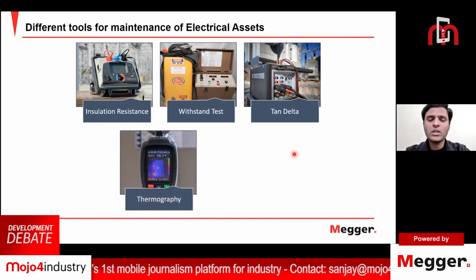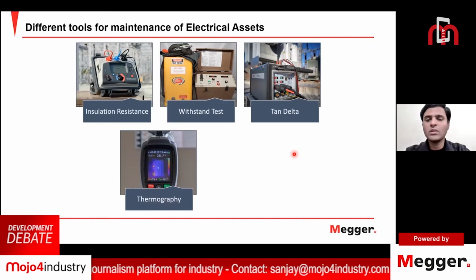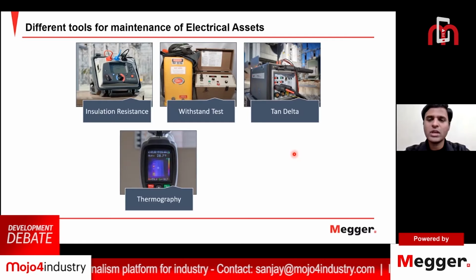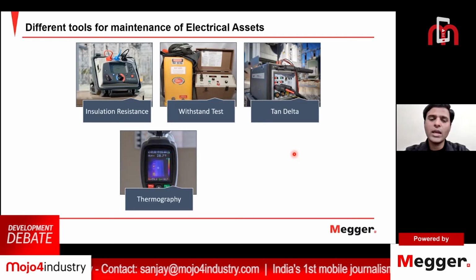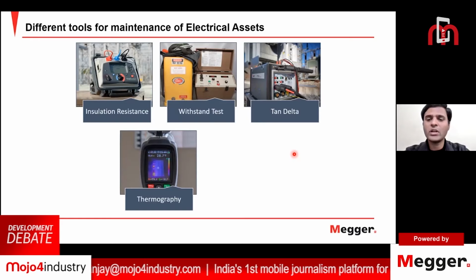Some of the industry experts say that we can identify the deterioration in electrical assets by doing thermography. Thermography is a principle in which thermographic cameras are based on infrared technology. It will give you the temperature of the surface of the target object, and if there is any deterioration in the electrical asset which has led to heating up of the target object, it will give you a temperature profile which will help you understand that there is high heat radiated from that particular asset. However, this high heat energy is radiated only at a later stage of deterioration.